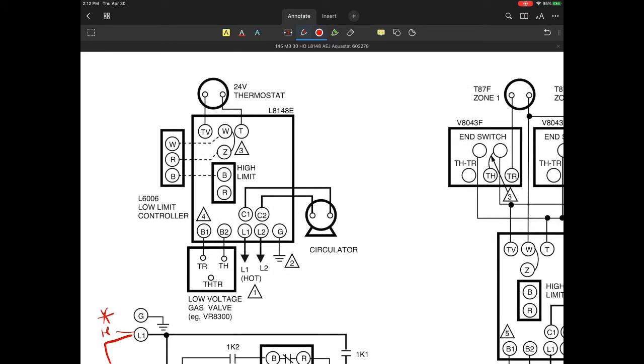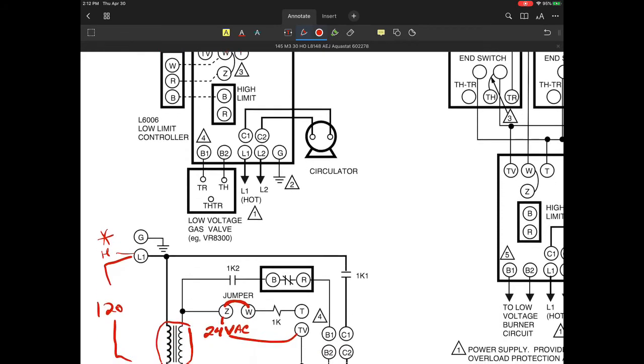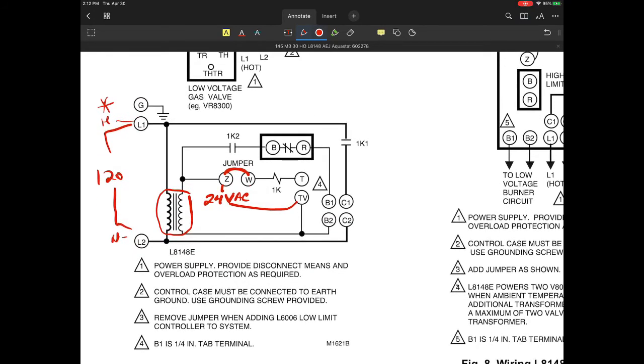You'll notice on here, let's say there's a thermostat demand, and I'm going to go to this diagram here. You'll see how they are identifying that 24 volt thermostat we talked about earlier. They're now using terminals TV and T. This may be an actual heating thermostat, or it could even be just a set of completely isolated relay contacts that goes between your TV and your T. That's how they're going to do this.